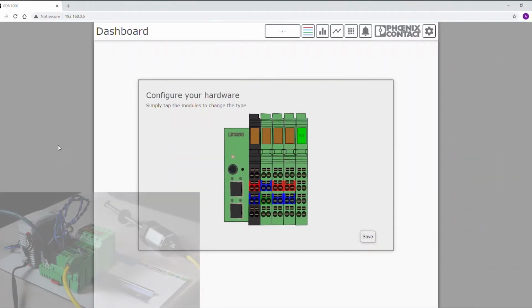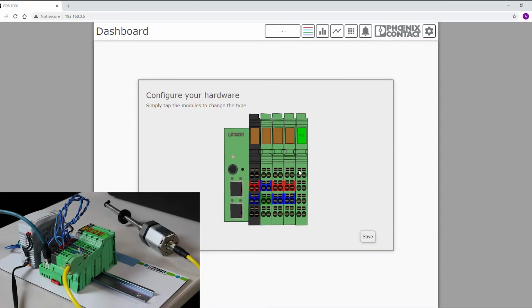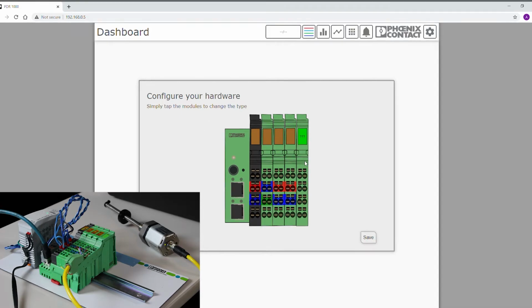So the first step when we pull this PDR out of the box, get it powered on, connected, and plugged in, is we open up our web browser and type in the IP address of the PDR. The first thing we see is this home configuration screen, where we set up and define our I/O. In our case, we added an analog input module that's going to be used to read a transducer position, so we need to define what type of module we have. We click on the image and select our analog input card—in our case, this is AI2.